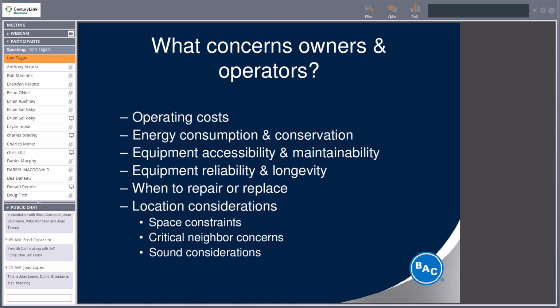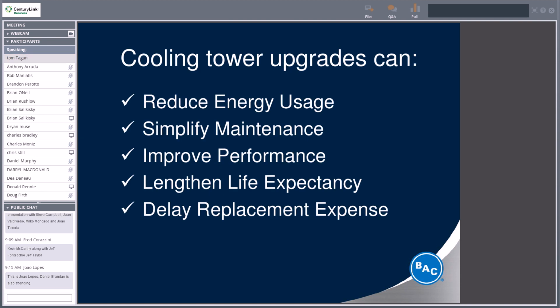So the concerns that owners and operators have are, the guys in the corner office are very concerned with operating costs. And along with operating costs come the energy consumption and conservation. The more fouled your system gets, the harder that chiller has to work, and the more expensive it costs to operate your building. So maintaining your cooling tower, again, I think I mentioned it at the onset of the presentation, it is not only to extend the life of it and to keep you guys busy elsewhere, but it's to operate your building as efficiently and less costly as possible. Cooling tower upgrades, you can reduce energy usage, simplify maintenance, improve performance, lengthen life expectancy, and delay replacement expense.